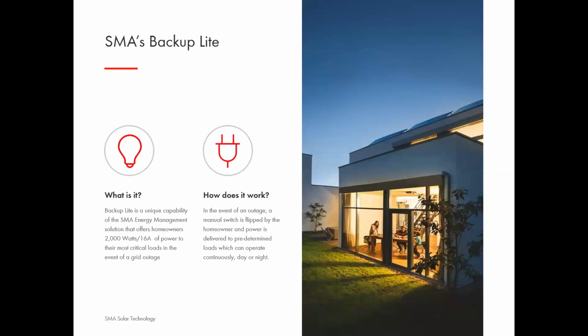So I want to tell you a little bit about Backup Lite, an enhancement to the secure power supply feature that you might be familiar with in our SunnyBoy product line. Secure power supply, for those of you that may not know, SMA is the first company in the world to develop a technology which allows a PV inverter to continue to supply AC electricity when the grid is down, and without actually injecting any power back into the utility lines through the meter.